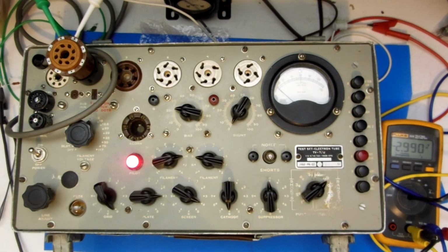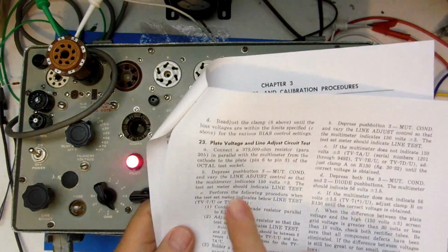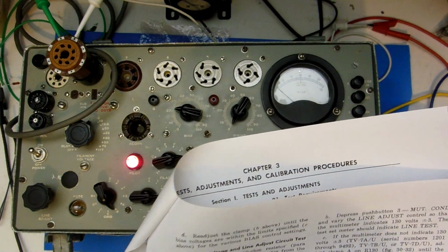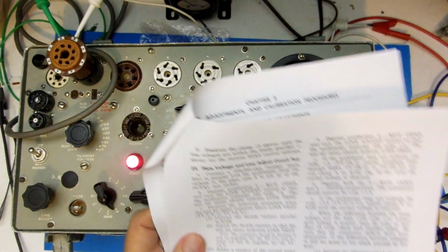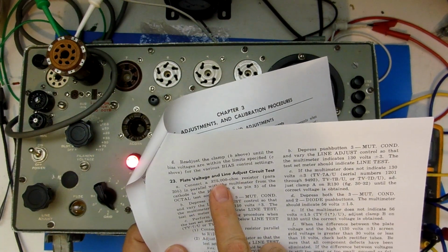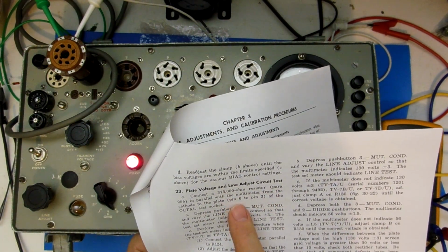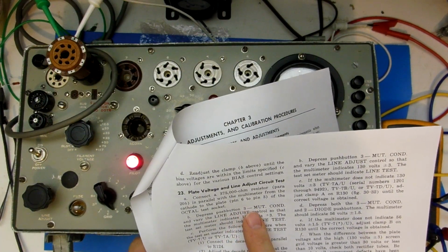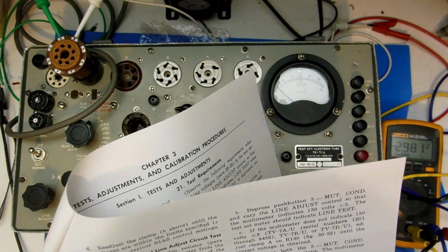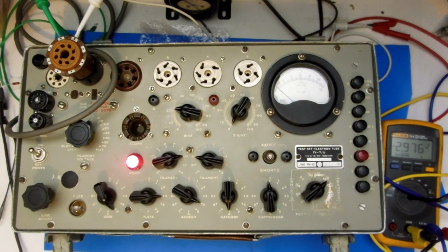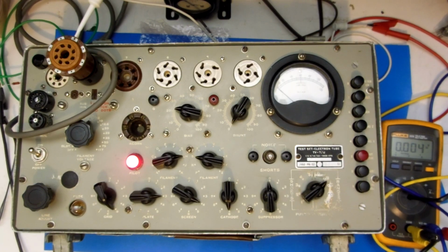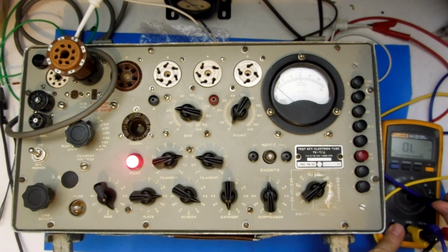And we'll go to section 23, which is plate voltage and line adjust circuit. Alright. So with this one, it says we want a 375 k ohm resistor in parallel with a multimeter from pins 6 to 3. Depress push button 3, and you should get 130 volts plus or minus 3. So let's set that up. Oh, disconnect this. I've got a potentiometer over here that I've set up to 375. So let's verify that. 375, that's close enough, 374.